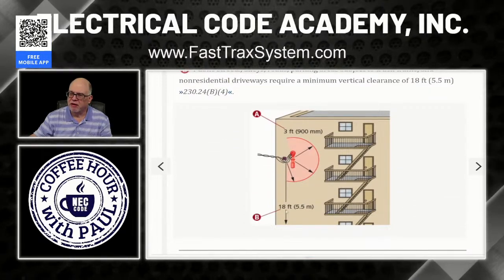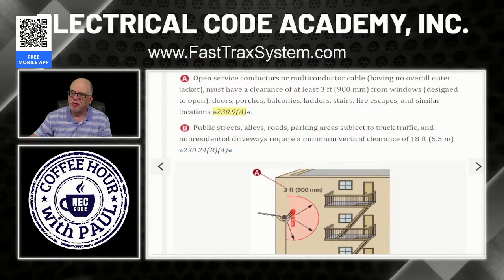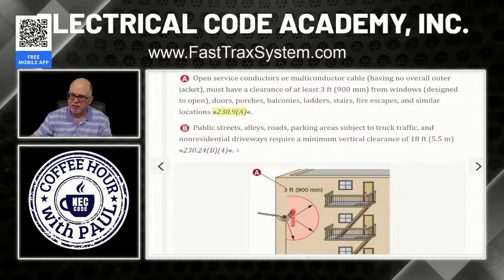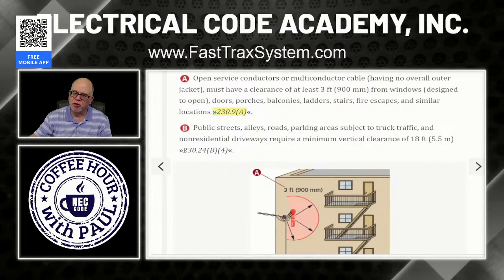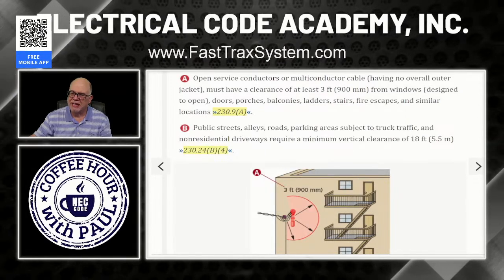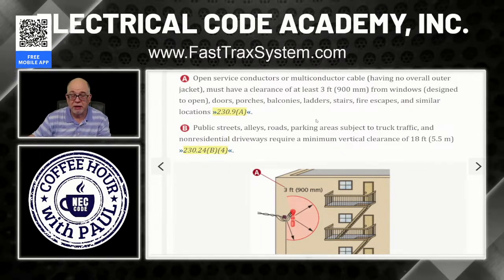So B is talking right here. This is a clearance. Public streets, alleys, parks, parking areas subject to truck traffic and non-residential driveways require a minimum vertical clearance of 18 feet. Now that's in 230.24(B)(4).